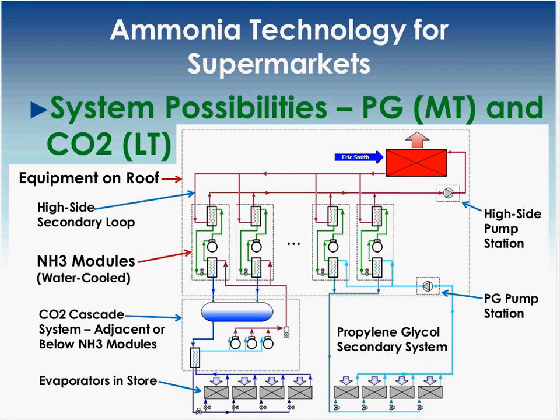So to the cooling portion here, obviously we would have the refrigerant shown here by the green line go to the ammonia carbon dioxide heat exchanger, and in this case it would be an ammonia to propylene glycol heat exchanger. But back to the low temp side, to the heat exchangers, multi-channel heat exchangers are becoming cheaper and more prevalent because of manufacturing techniques, and this is allowing the industry, both the industrial and the commercial industry, to create machine houses with a much smaller footprint and still be very efficient.